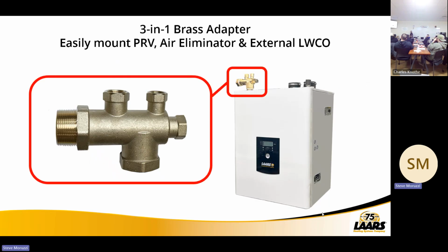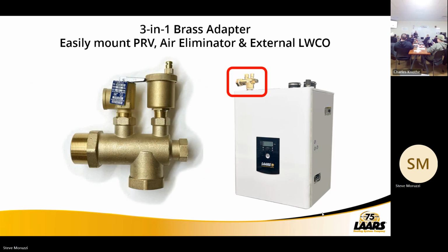So this is really a 4-in-1 brass adapter, even though I have it listed as a 3-in-1. It's got multiple taps, so you can use your air elimination and relief valve. These all come with the boiler. You can put your low water cutoff here on the right-hand side and wire that in. And this fitting here is off the top of the boiler, so this connection will be feeding out to the system.